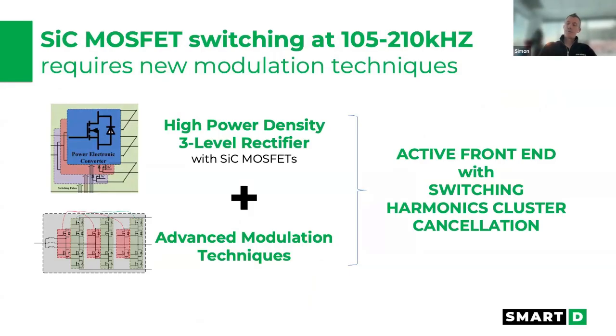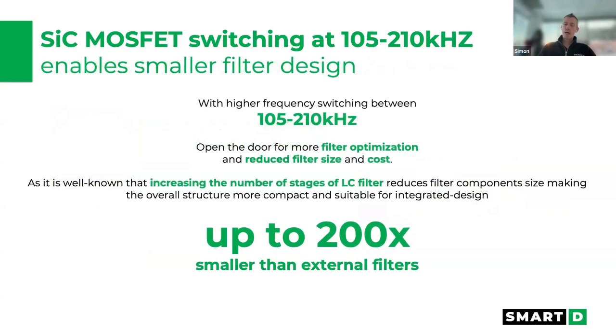We integrated into that some switching harmonics cluster cancellation. This is purely mathematical, so don't ask me a question on that. I don't really understand it. Some much smarter guys on my team are doing that. We also used a 3-level architecture instead of your typical 2-level architecture. And what you have is an output of 210 kilohertz, but more importantly, we are able to reduce the size of the filter by a factor of 200. So, we say it's filterless for the user, but it's a little bit of a trick, because we actually have very small filters built into the drive.